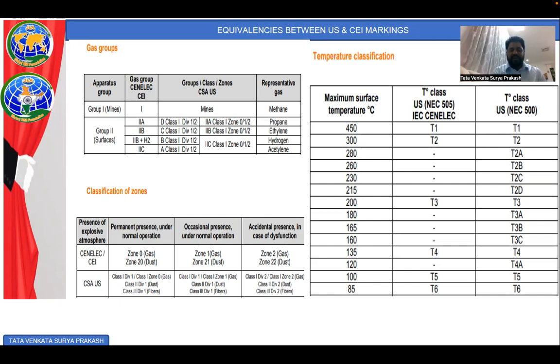And in the case of CSA US, a class is given, class, division, class 2, class, zone 0, etc. is given. So more or less the conditions of manufacturing may all be the same, but in the marking he has to take care, and some testing and certification requirements may vary from country to country based on national regulations. So the manufacturer or the end user has to coordinate to understand and comply with the requirements.